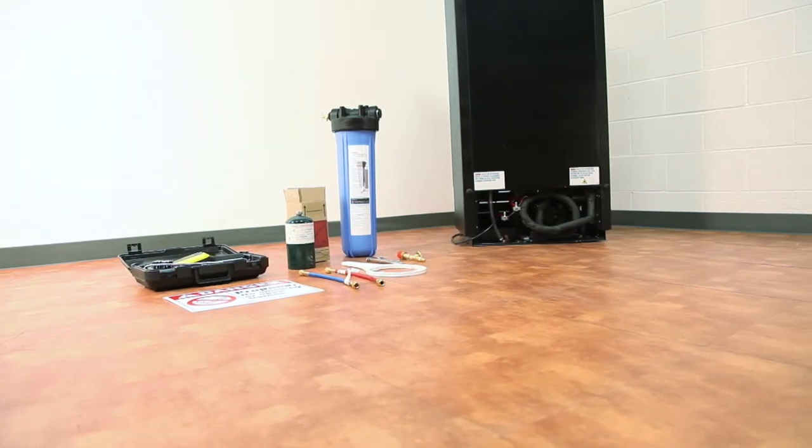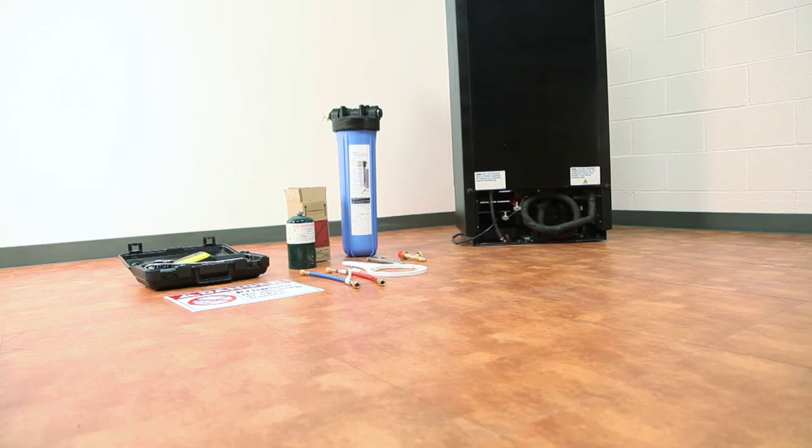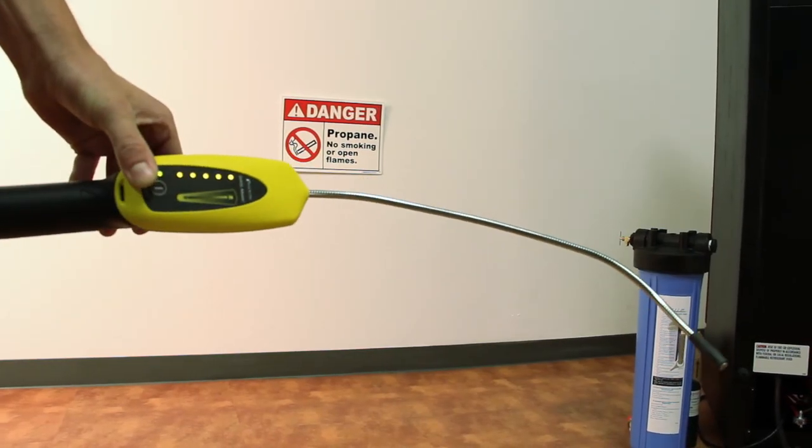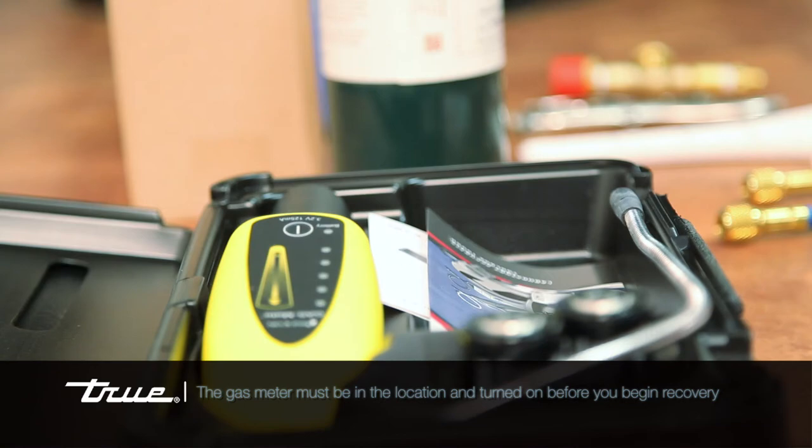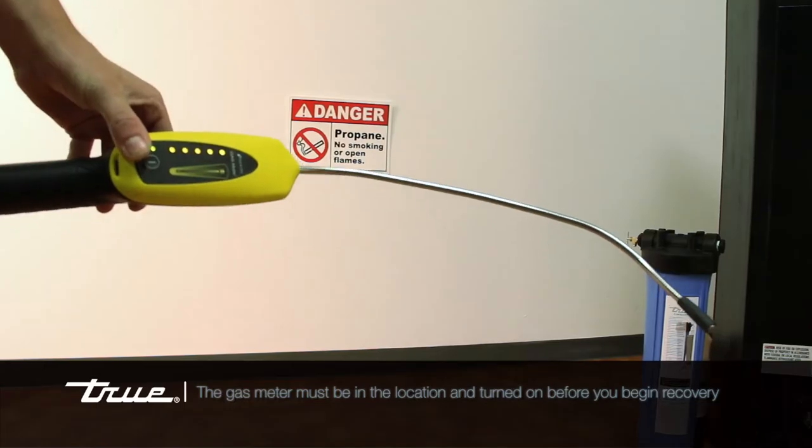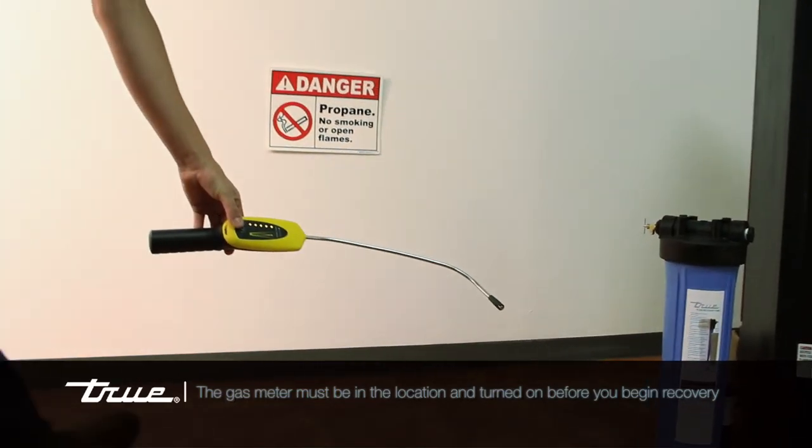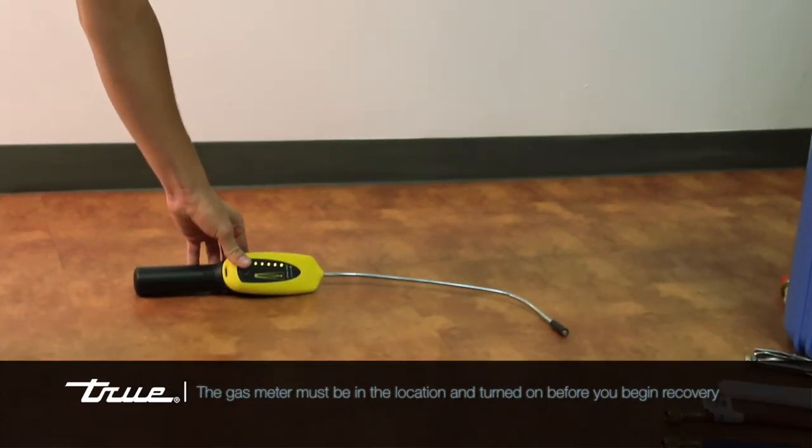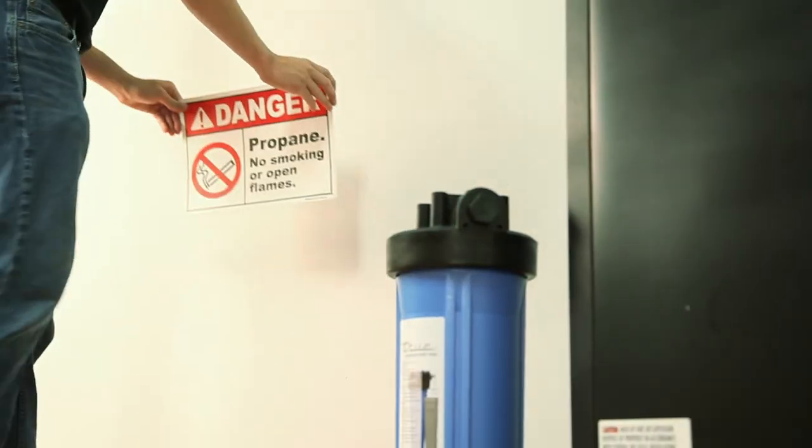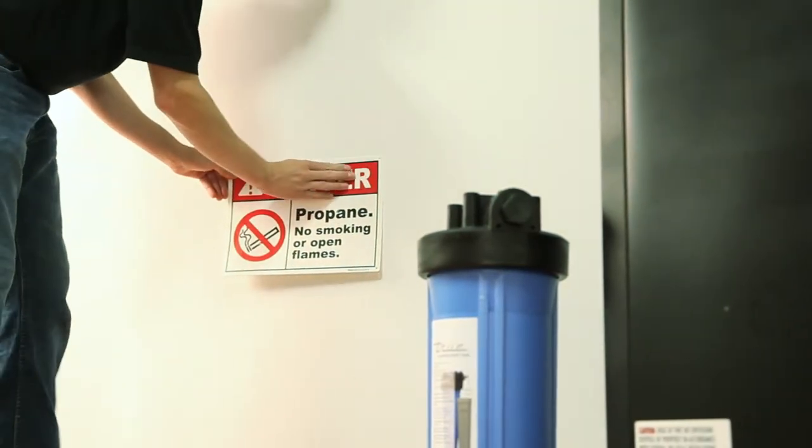The recovery process or any refrigeration related repair should start by turning on your gas meter or leak detector. This tool is also part of the HC Toolkit. This should remain on until the repair is completed. The safety placard needs to be in a location where the recovery or repair is taking place.